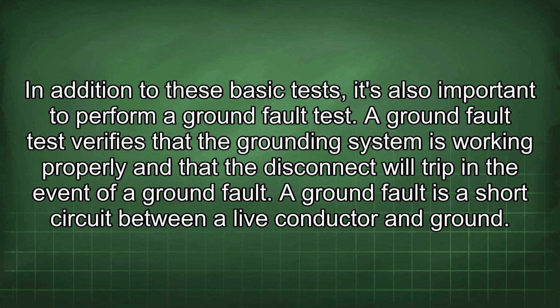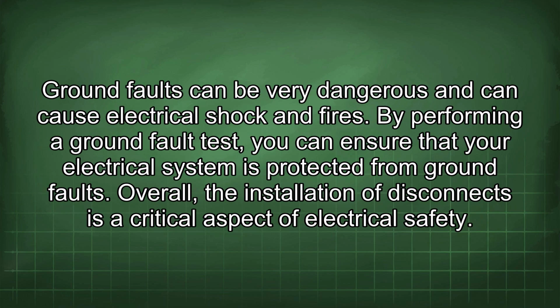In addition to these basic tests, it's also important to perform a ground fault test. A ground fault test verifies that the grounding system is working properly and that the disconnect will trip in the event of a ground fault. A ground fault is a short circuit between a live conductor and ground. Ground faults can be very dangerous and can cause electrical shock and fires. By performing a ground fault test, you can ensure that your electrical system is protected from ground faults.